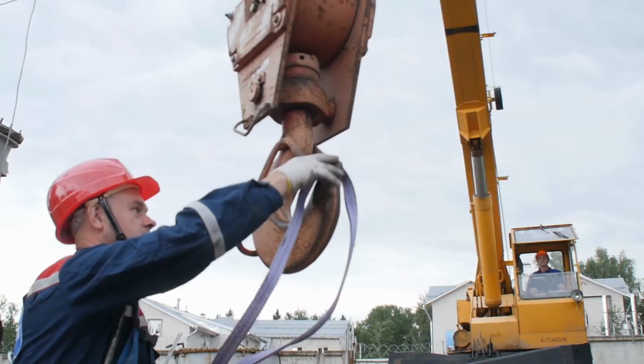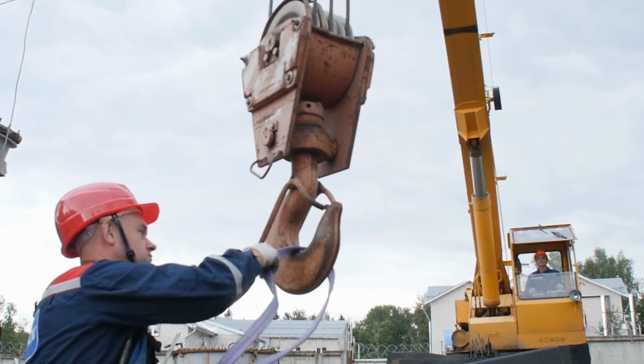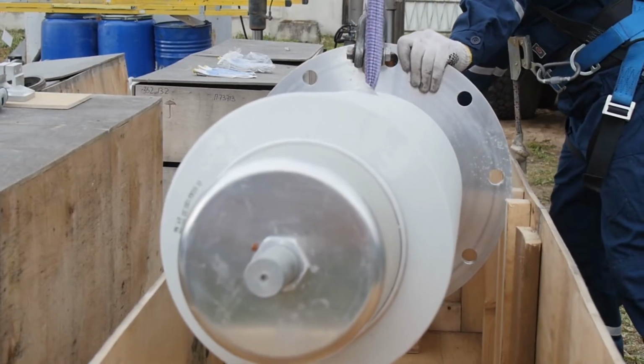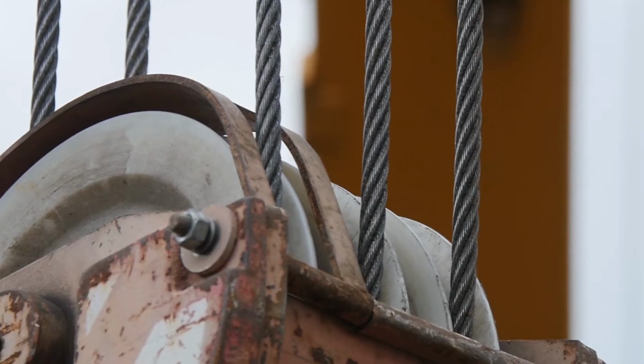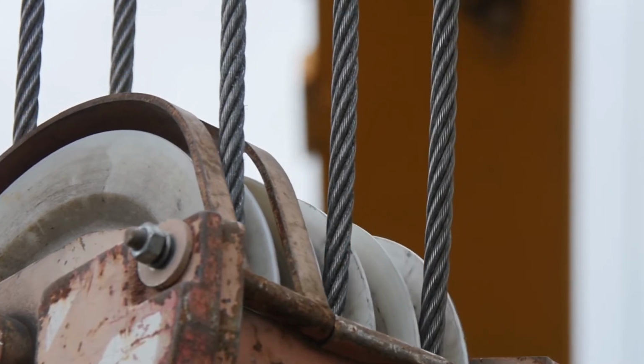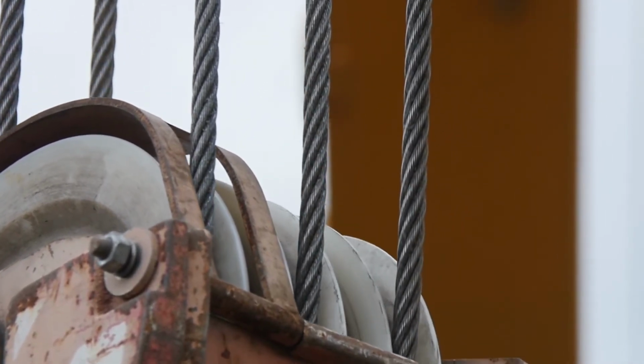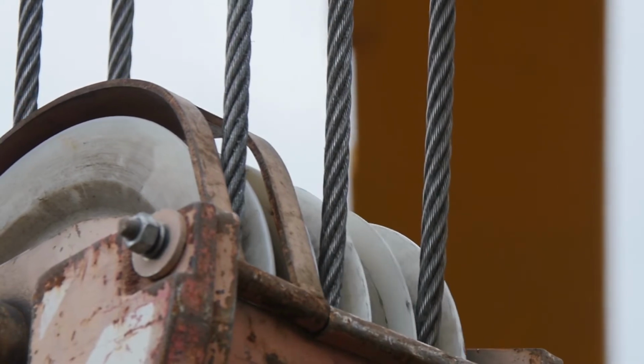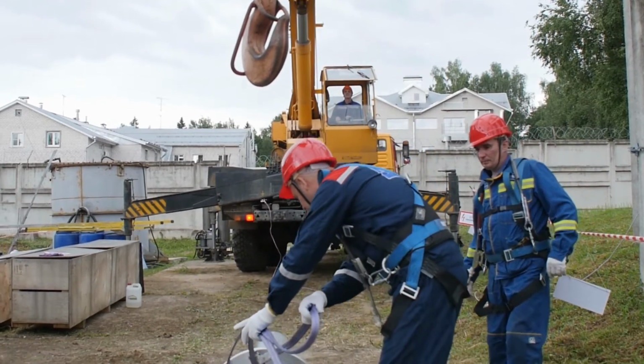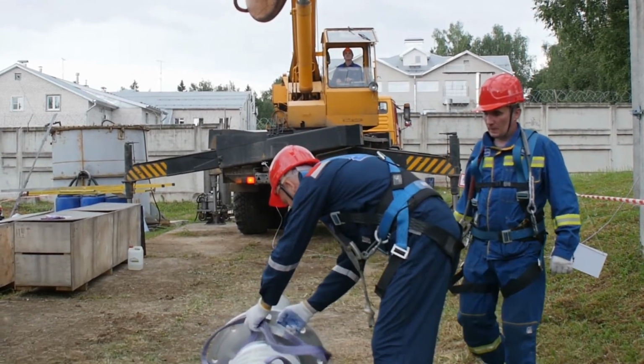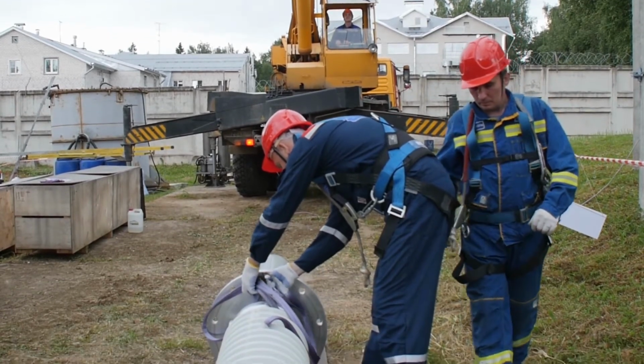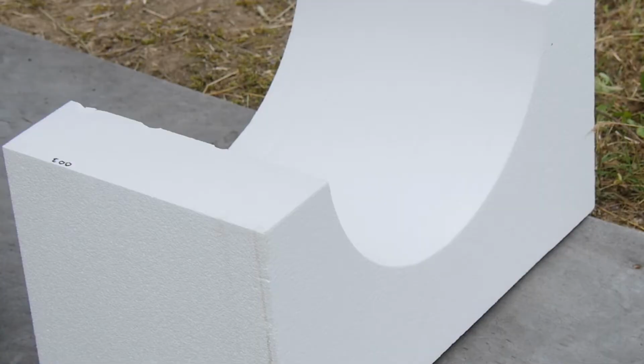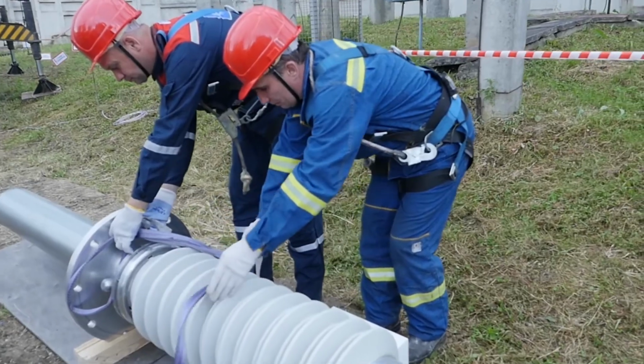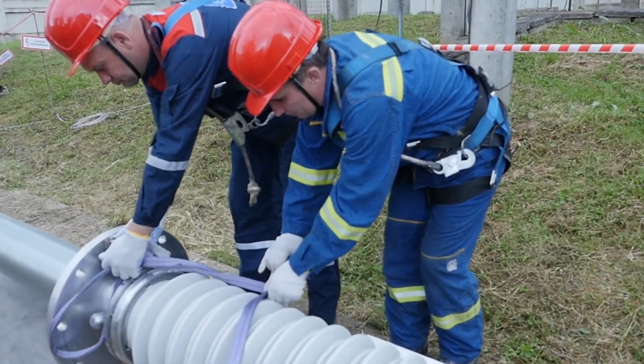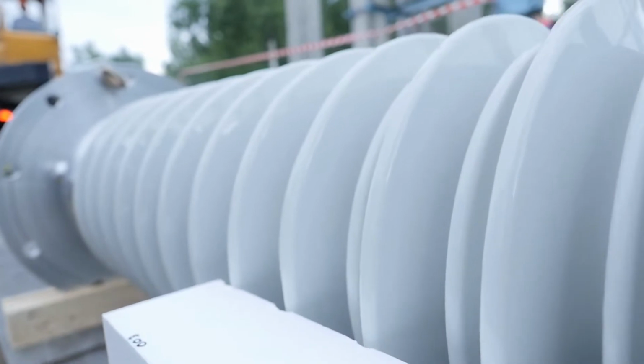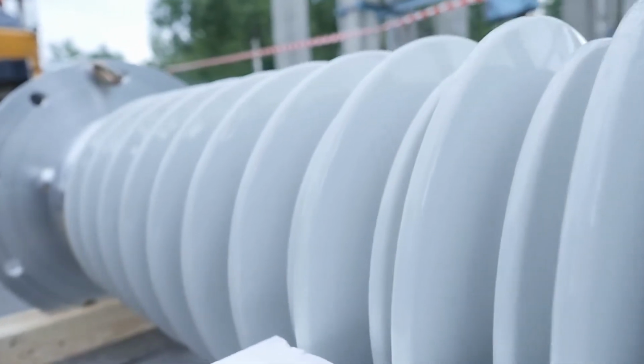Smoothly lift the bushing over the package to a minimum height and make sure it is leveled. If not, put it back in and tie up the bushing using other sheds of the housing. Only then can the bushing be removed out of the package and handled further. Put the bushing down with the porcelain housing resting on the polystyrene foam supports taken out of the package earlier. When setting the bushing horizontally, make sure it rests on the same points as in the package.